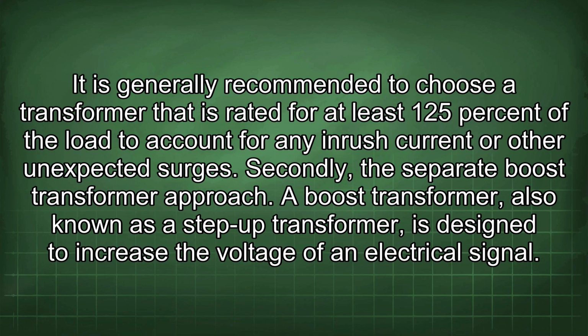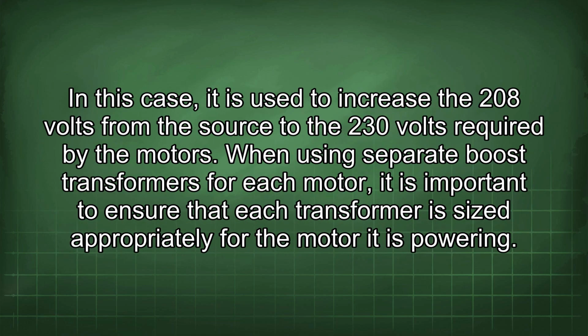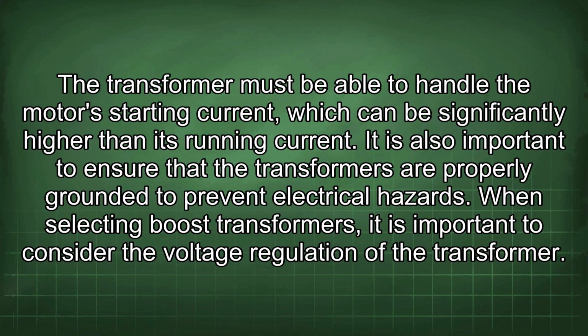Secondly, the separate boost transformer approach. A boost transformer, also known as a step-up transformer, is designed to increase the voltage of an electrical signal. In this case, it is used to increase the 208 volts from the source to the 230 volts required by the motors. When using separate boost transformers for each motor, it is important to ensure that each transformer is sized appropriately for the motor it is powering. The transformer must be able to handle the motor's starting current, which can be significantly higher than its running current. It is also important to ensure that the transformers are properly grounded to prevent electrical hazards.